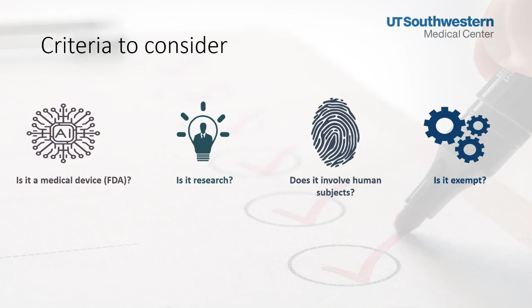I actually used this with staff just yesterday. We went through a scenario on whether the software could be considered a medical device. There are very helpful decision trees on the FDA's website, but specifically the FDA is looking at medical devices as software that's intended to be used for one or more medical purposes and performs those purposes without being part of some type of hardware system. And in those situations, because it's a medical device and it's defined as such, IRB review would be required.